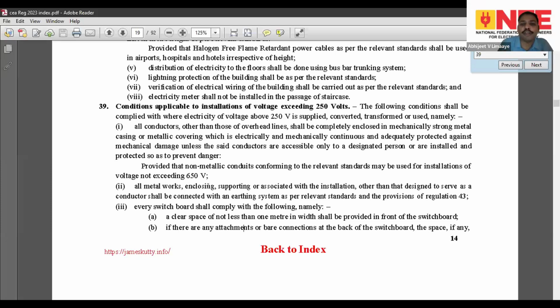You need to have a space of 1 meter in front of the panel. And when talking about rear access, either you close it off, have no rear access, or have it less than 20 centimeters. In case you want rear access, it should be at least 750 millimeters, plus you need a walkway so that rear access can be easy.